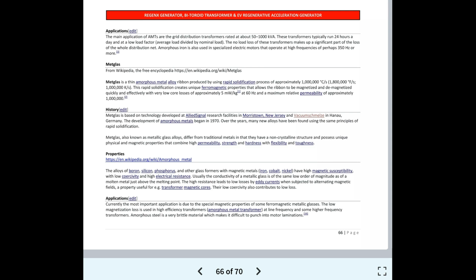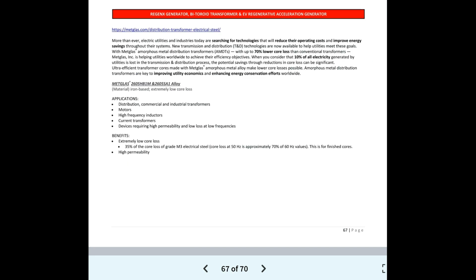Applications. Currently the most important application is due to the special magnetic properties of some ferromagnetic metallic glasses. The low magnetization loss is used in high-efficiency transformers, amorphous metal transformer, at line frequency, and some higher frequency transformers. Amorphous steel is a very brittle material, which makes it difficult to punch into motor laminations. More than ever, electric utilities and industries today are searching for technologies that will reduce their operating costs and improve energy savings throughout their systems. New transmission and distribution, T&D, technologies are now available to help utilities meet these goals.